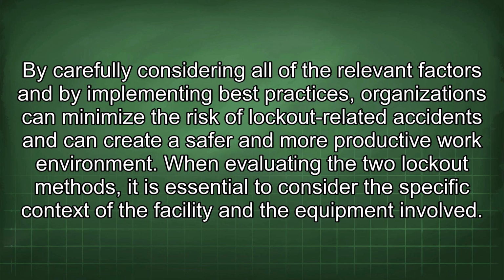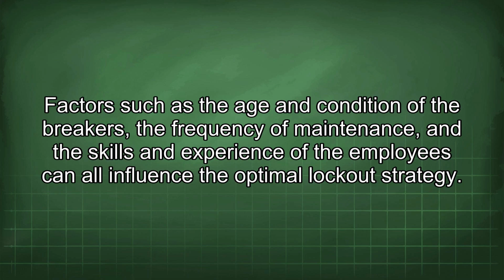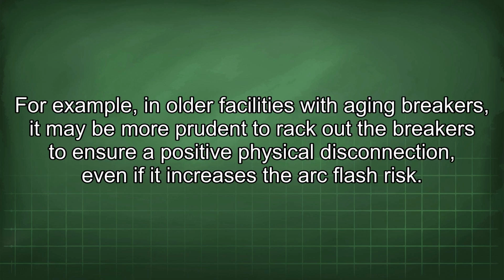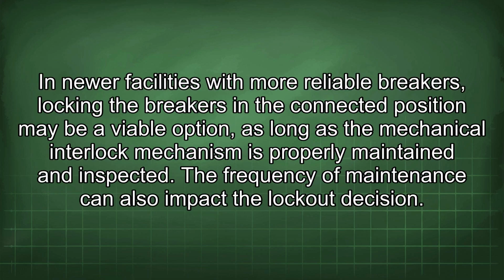When evaluating the two lockout methods, it is essential to consider the specific context of the facility and the equipment involved. Factors such as the age and condition of the breakers, the frequency of maintenance, and the skills and experience of the employees can all influence the optimal lockout strategy. For example, in older facilities with aging breakers, it may be more prudent to rack out the breakers to ensure positive physical disconnection, even if it increases the arc flash risk. In newer facilities with more reliable breakers, locking the breakers in the connected position may be a viable option as long as the mechanical interlock mechanism is properly maintained and inspected.